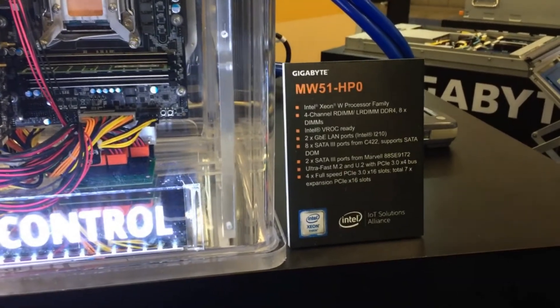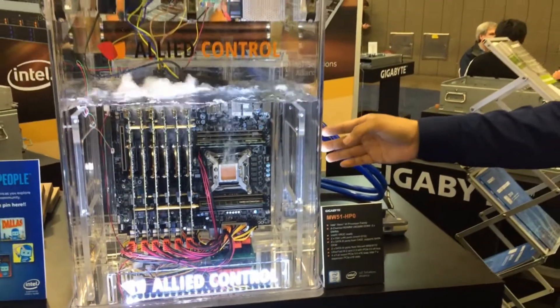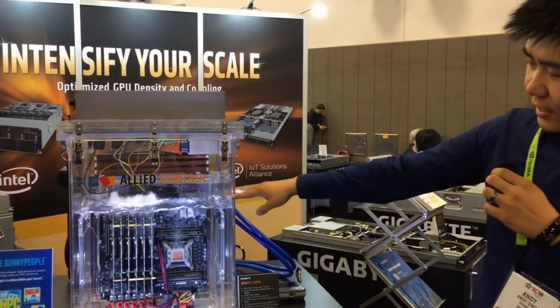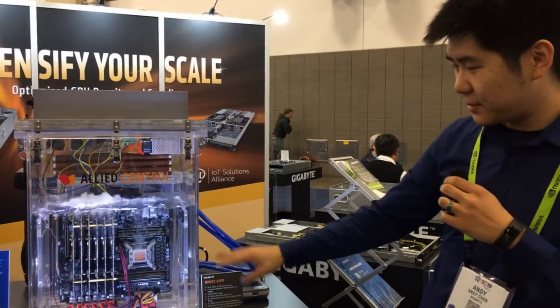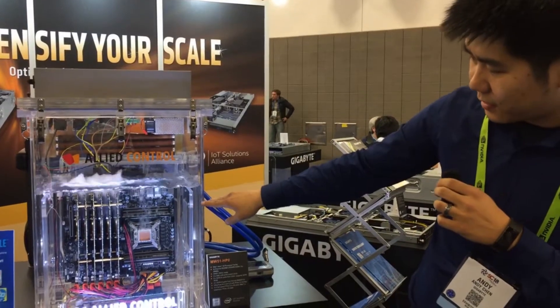You can see the system is completely immersed inside a liquid developed by 3M, and we partner with Allied Control — their name's right here. The liquid has a boiling point around 56°C and it keeps everything cool, including all the chipset, the capacitors, and the breakers.